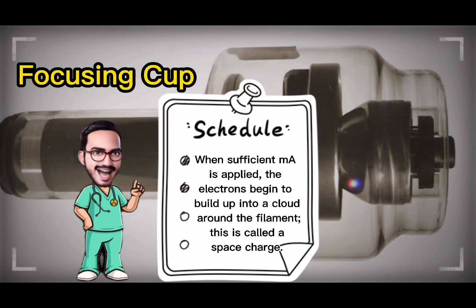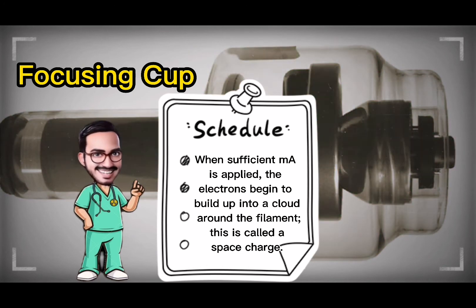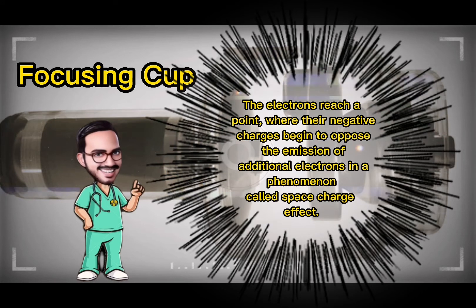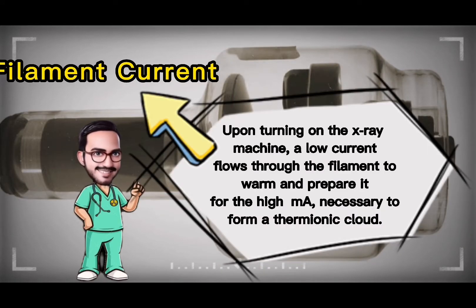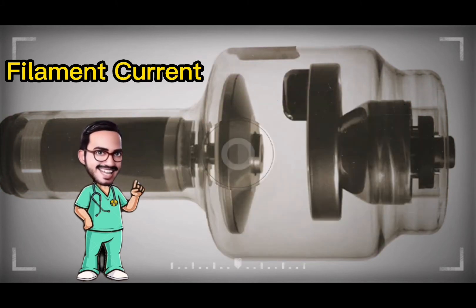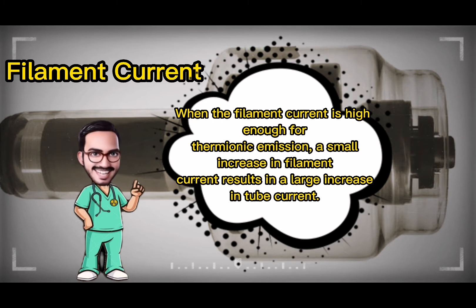When sufficient mA is applied, the electrons begin to build up into a cloud around the filament — this is called a space charge. The electrons reach a point where their negative charges begin to oppose the emission of additional electrons, in a phenomenon called the space charge effect. A low current flows through the filament to warm and prepare it for the high mA necessary to form a thermionic cloud. When the filament current is high enough for thermionic emission, a small increase in filament current results in a large increase in tube current.